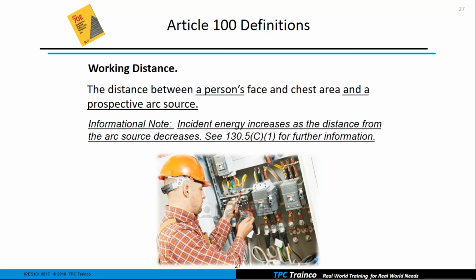Working distance, they played just a little bit with, and I find that when I teach live seminars, a lot of people just don't understand working distance. Basically, this is where we make a prediction of how much energy is going to come at the person's face and chest area. If we are below 1,000 volts, that working distance is usually 18 inches away. So we have to understand, okay, at 18 inches away, we made a prediction of 7 calories per centimeter squared of incident energy. Well, that's great.